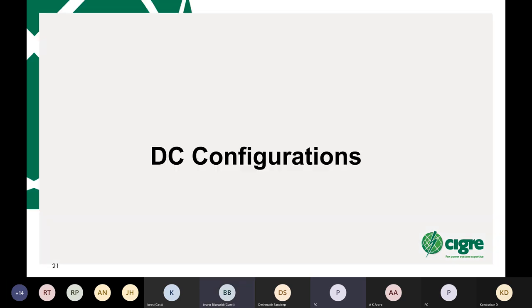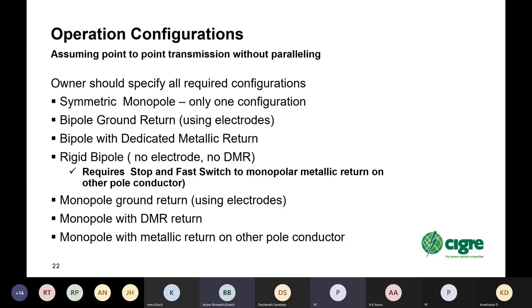So having specified that, we can move on to DC configurations. And so first looking at operating configurations, assuming point-to-point transmissions without parallel converters or parallel HVDC systems, the owner should specify all of the required configurations. Symmetric monopole only has one configuration. Basically, it operates when it's on or off. Bipole ground return using electrodes, of course, that may have monopolar operation, bipolar operation, bipole with dedicated metallic return, similar rigid bipole. With the rigid bipole, requires a fast stop and switch to monopolar metallic return on the other pole conductor if you have a pole fault.